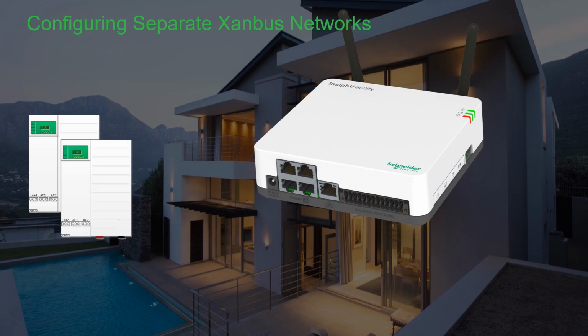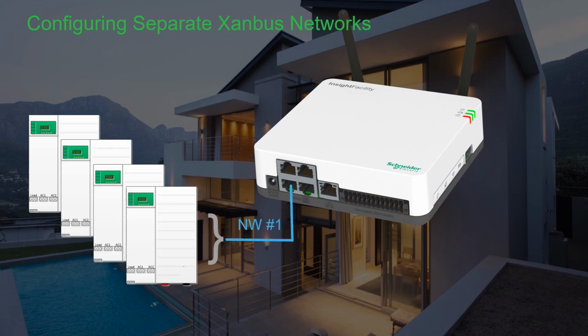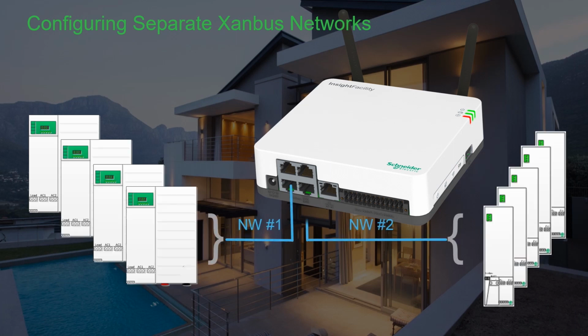4 XW Pros takes up a significant amount of bandwidth for a single Xanbus network. You will easily have enough extra bandwidth to add a battery monitor and an AGS. However, you will not be able to add charge controllers to the same Xanbus network as the quad stack. For large DC-coupled systems such as this, use the secondary Xanbus network of InsightFacility, which will aggregate the devices from both Xanbus networks to a single web page on Insight Local and on Insight Cloud.